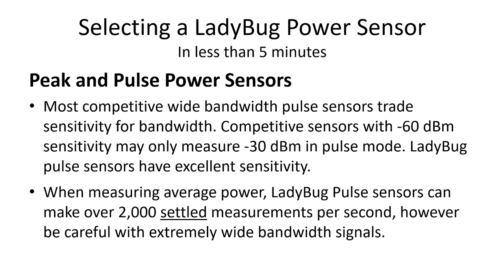It's important to understand all the specifications of the peak and pulse power sensor you're considering. Most competitive wide bandwidth pulse sensors trade sensitivity for bandwidth. They may advertise minus 60 or minus 70 dBm. However, they can only do that in average mode. When you put the sensor in pulse mode, the video filter opens up, allows noise in, which brings the noise floor up to minus 35 or so dBm in the pulse mode. Our sensors measure minus 60 dBm in pulse mode.